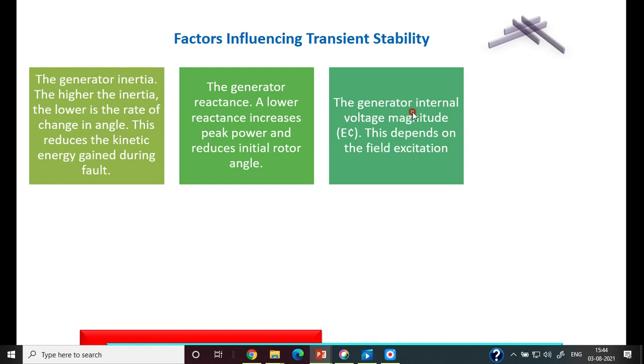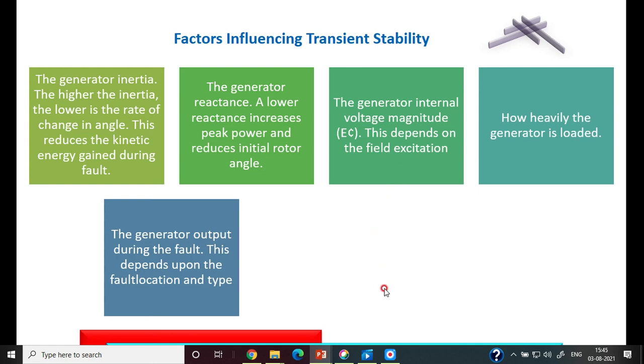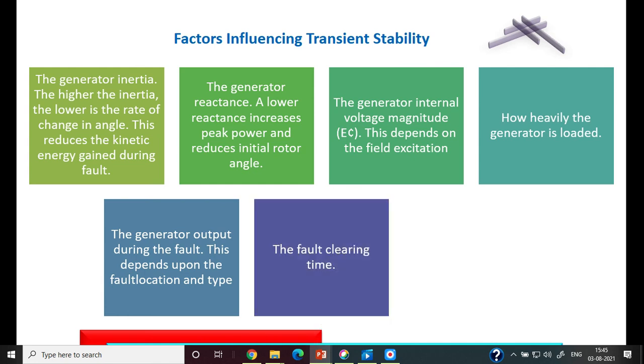Third, the generator internal voltage magnitude E', which depends on the field excitation and also on how heavily the generator is loaded — both affect transient stability. Fourth, the generator output during the fault, which depends on the fault location, type, and the reactance up to the fault point. Fifth, fault clearing time — the fault must be cleared so that delta does not exceed the critical clearing angle, and the corresponding time is called the critical clearing time (TCR).